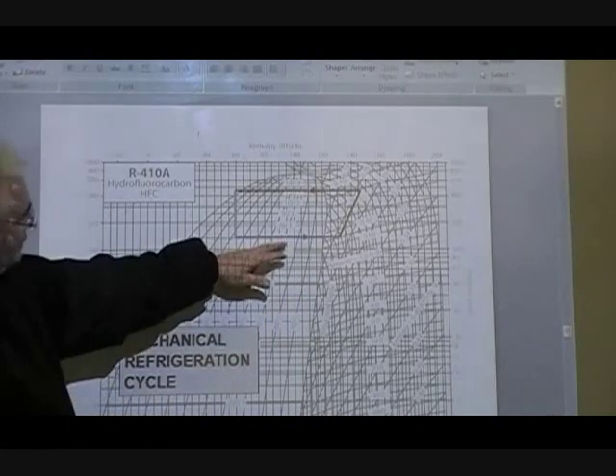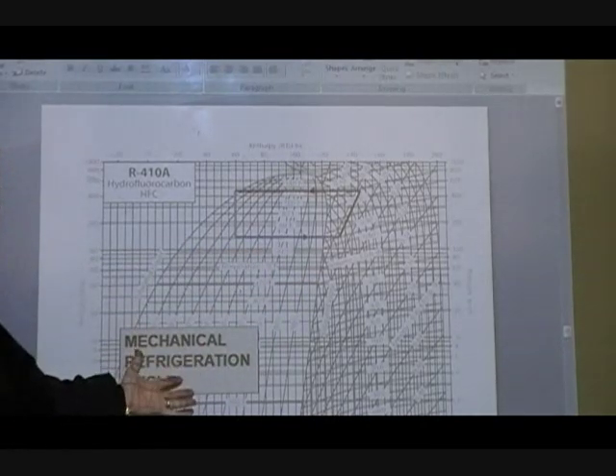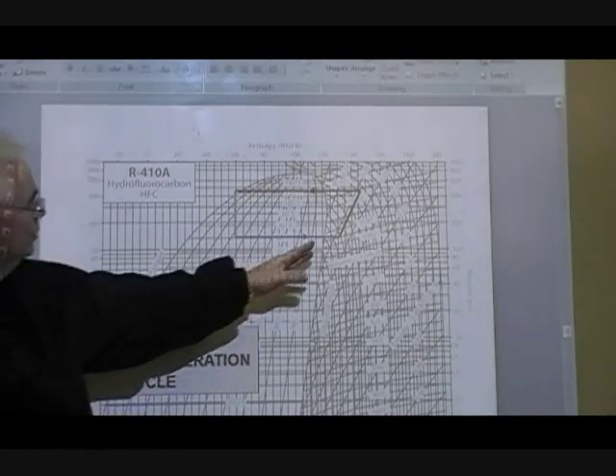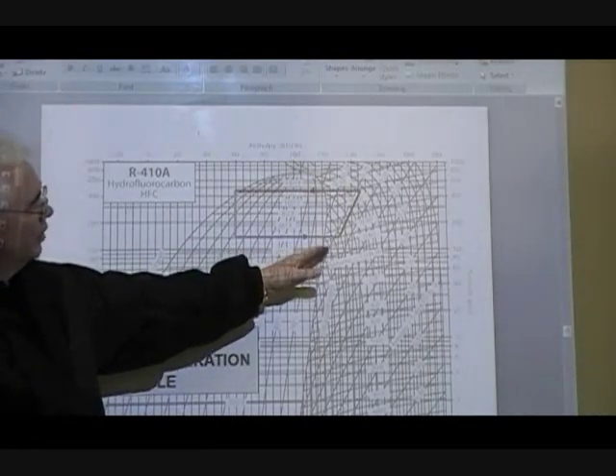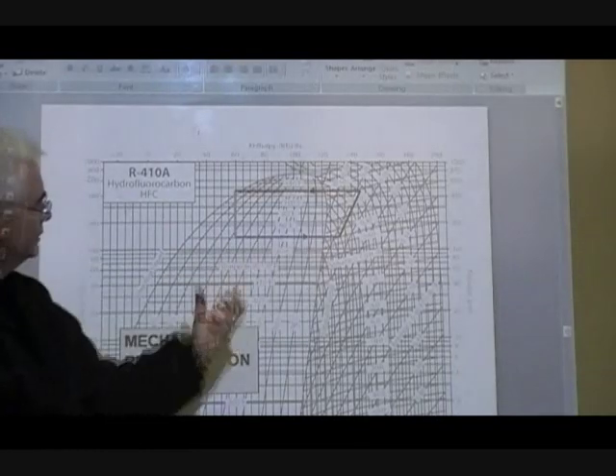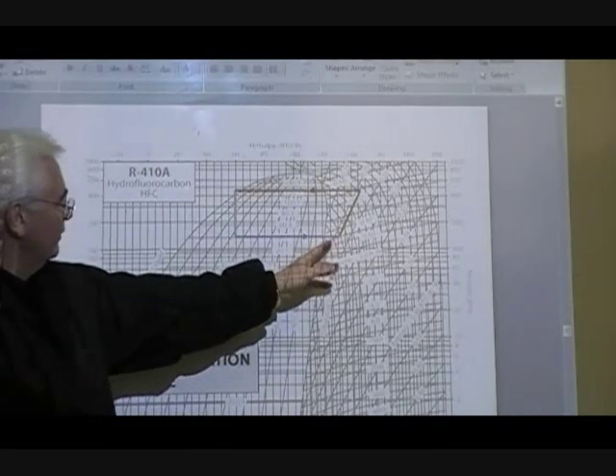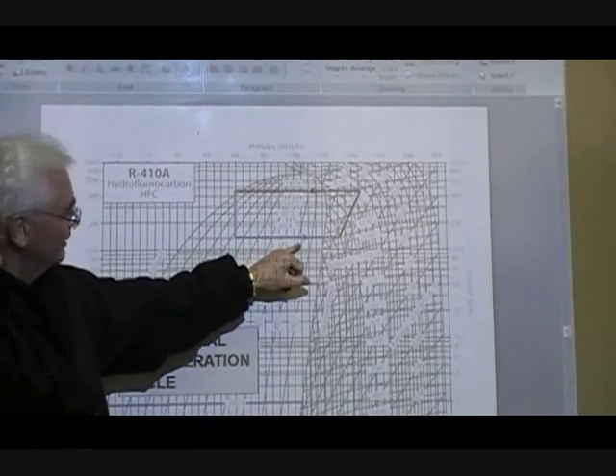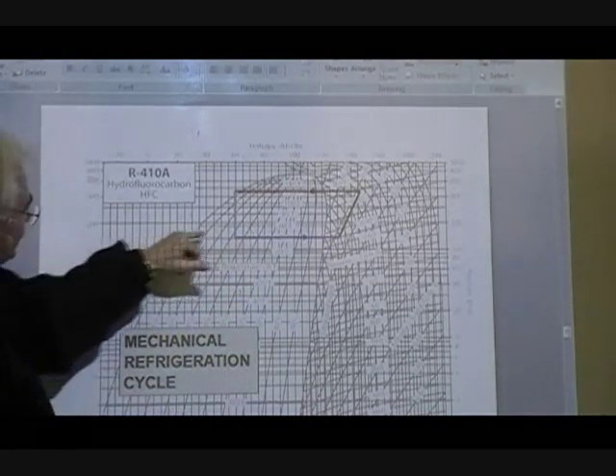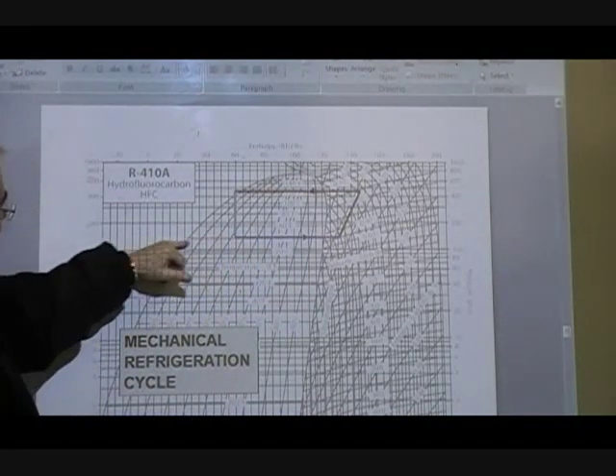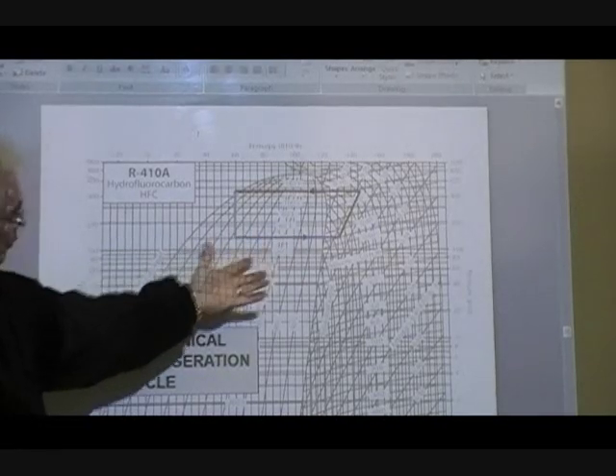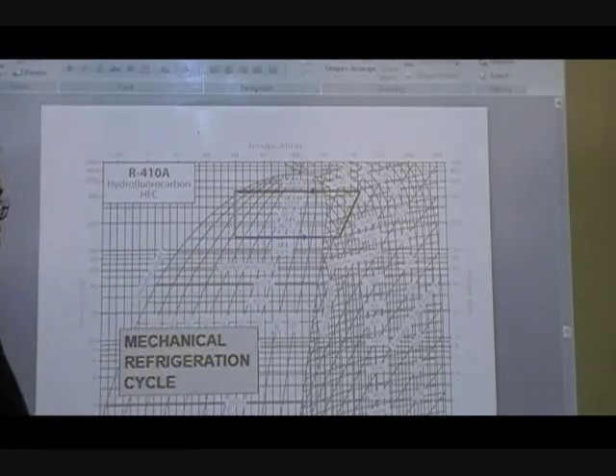What's the point of saturation? 40 degrees. Let's say, in this scenario, you've got 10 degrees of superheat. Your suction line coming off the evaporator is going to be about 50 degrees if you measure it with a thermometer. You've got a 50 degree suction line coming off the evaporator. You've got a 40 degree saturated vapor temperature. How do you know that? By your pressure. Look at your suction pressure, convert to temperature, which they do that for you on the pressure-enthalpy diagram. And so you know that you've got 10 degrees of superheat. It's not really hard to figure out.